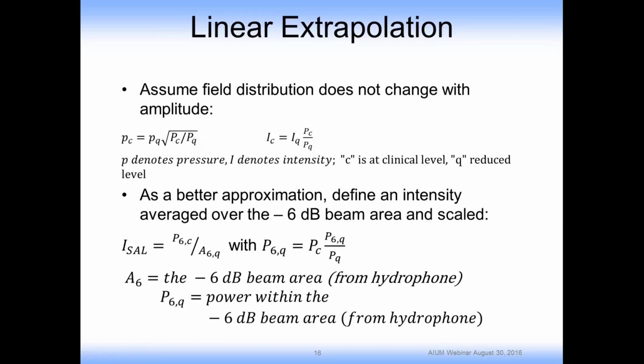If you remember from the earlier slide, where pressure squared determined intensity, you can see that the pressure should go as the square root of the power. So that's why this scaling approach is used here. Now, as I mentioned, this all assumes that the distribution of the field does not appreciably change. And in fact, it can in some cases. So as a better approximation, you can average out the change in the shape of the field by taking an average of the intensity along the 6 dB area of the beam, and that's where this ISAL concept comes in. Basically, you measure the power contained within the 6 dB area and divide by the area of the 6 dB area.